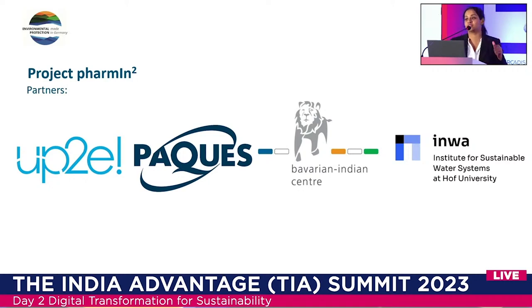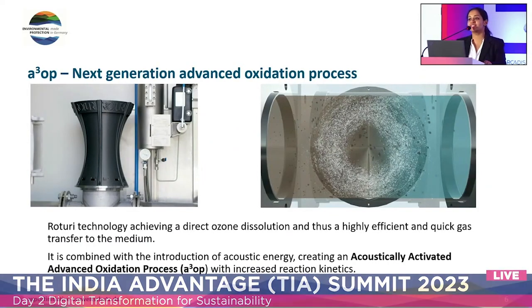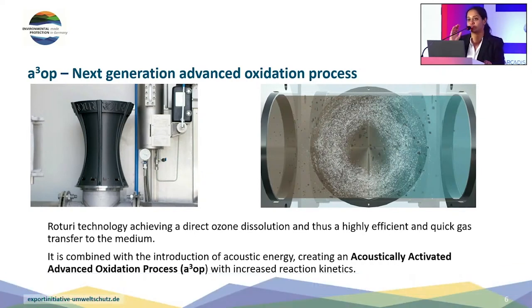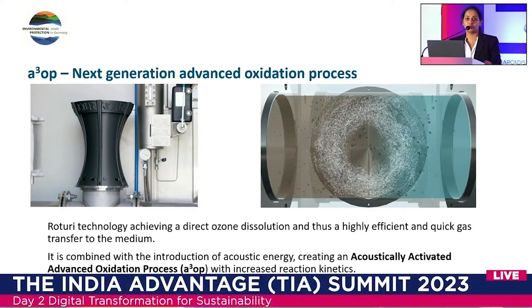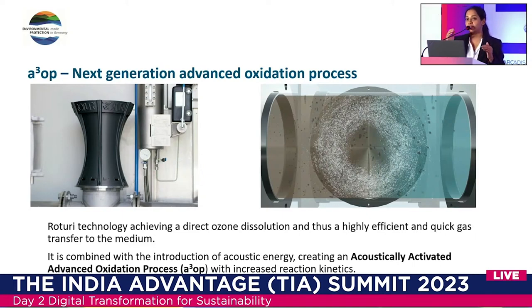Moving on to the technical aspects — triple AOP can be defined as the next generation advanced oxidation process. An advanced oxidation process is a chemical treatment done to water to convert contaminants into non-toxic substances, using hydroxyl radicals. In triple AOP, there is a device named Roturi through which complete and efficient dissolution of ozone is achieved into the medium — in our case, pharmaceutical wastewater. Along with this, acoustic energy is also introduced into the system, creating an acoustically activated advanced oxidation process.